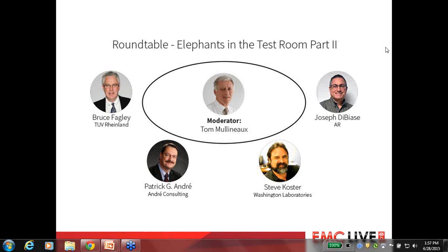So talking of calibrations and so forth, the title of our second elephant for today is the search for a golden emissions test setup proving emitter for use in 3-meter chamber tests. And the abstract reads, the use of a comb generator's output signature is a good method for checking all is well with an emissions test setup, but in reality simply proves the test system is consistent in providing the same wrong readings as before.